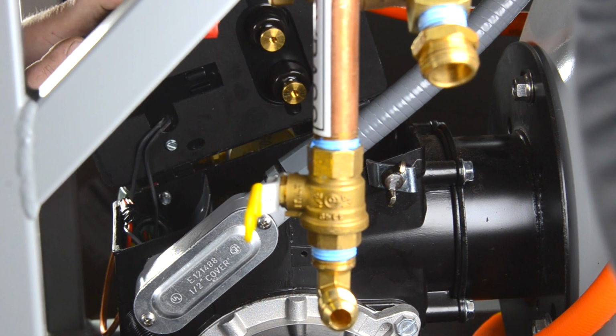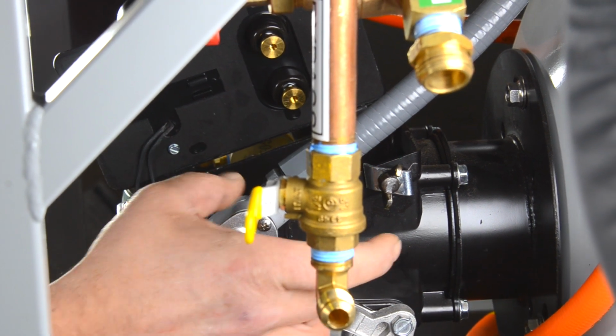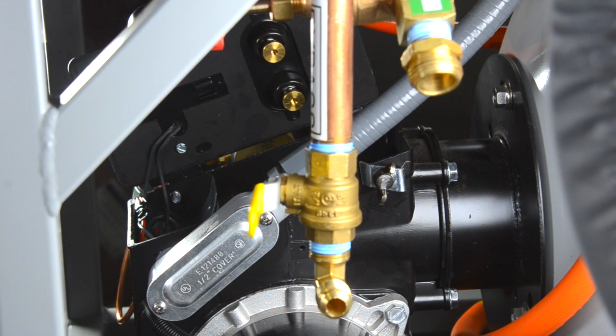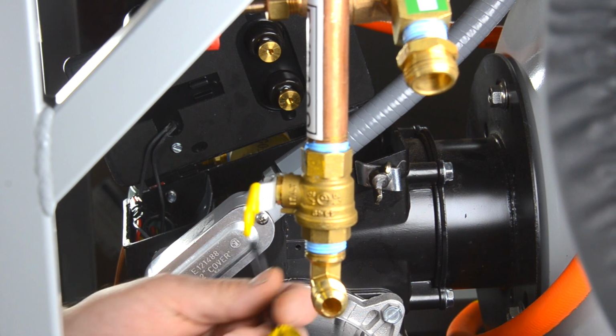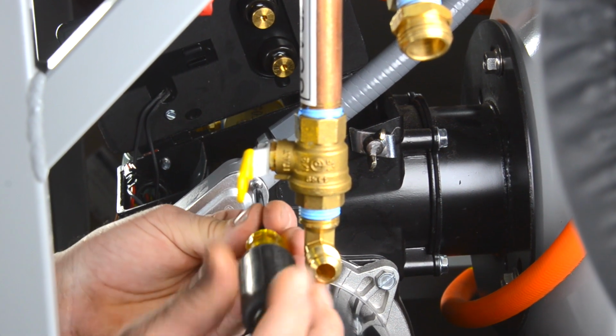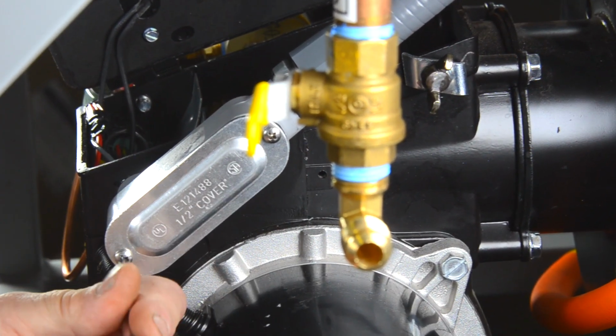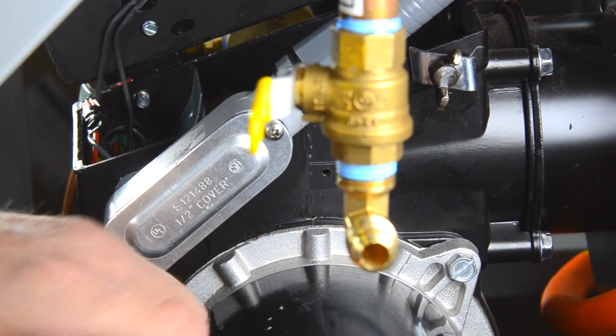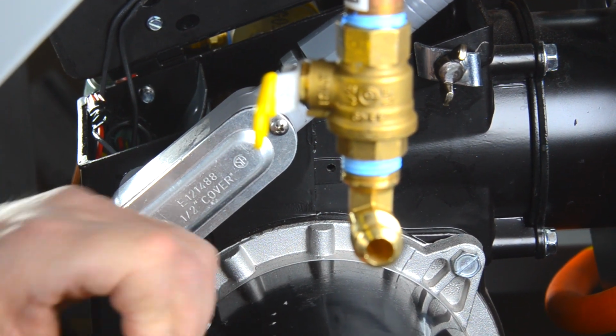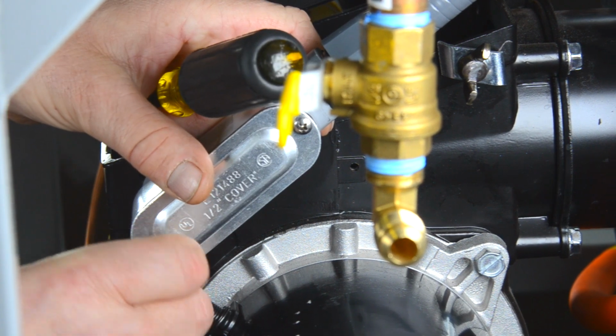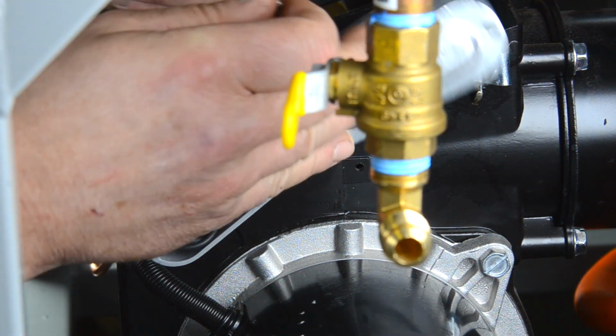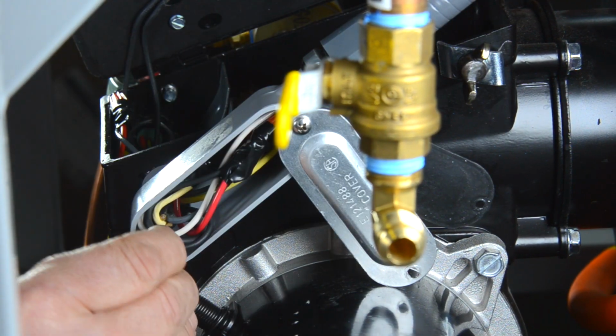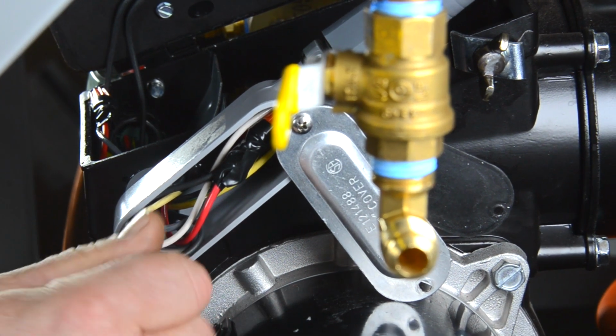Okay, open our transformer. Now you're going to locate your LB box here, the one with the conduit coming down from the top. We're going to loosen your top screw. Remove the bottom screw. Take that out carefully. Just pivot your lid out of the way so you can't drop it and lose it. We're just going to put that screw back in the hole for now.